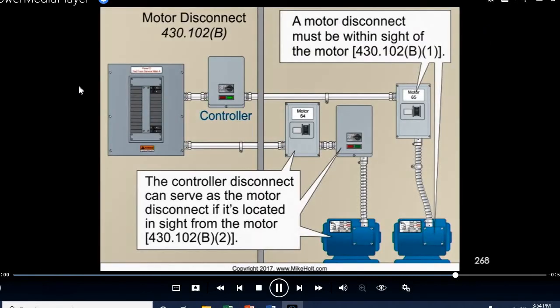Now, a motor disconnect. The controller disconnect can serve as the motor disconnect if it's located in sight from the motor. So here's the controller disconnect. And if the controller disconnect is within sight of the motor, then I don't need to have a separate disconnect for the motor, because the controller disconnect can serve as the motor disconnect. Now, you need a disconnect within sight of the motor, and that's another way to do it. Just simply put a disconnect within sight of the motor, and put a disconnect within sight of the controller. These are the rules of being within sight.